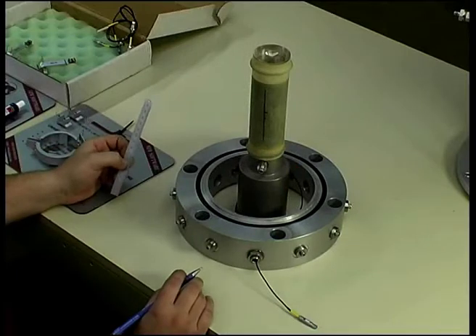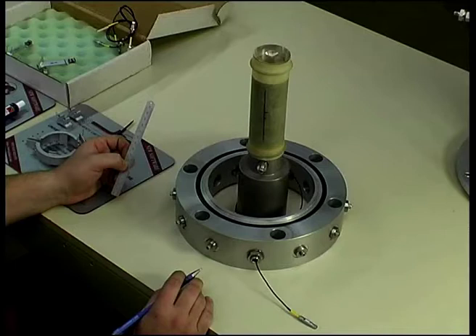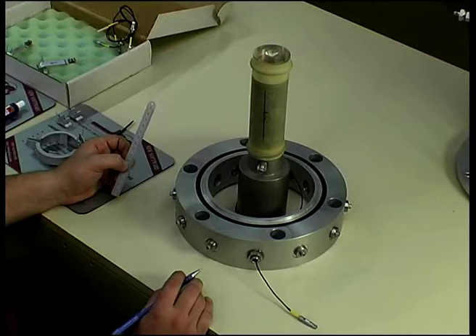To enable us to mark the position of the axial pads, we must first set the gauge length to the desired length. The gauge length may be adjusted to suit your requirements from close to one third of the sample height to two thirds of the sample height by rotating the magnet foot. Once we have established the gauge length, we can mark the position of the vertical pads.